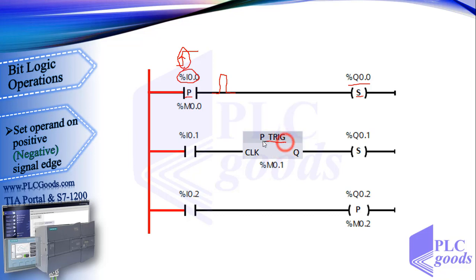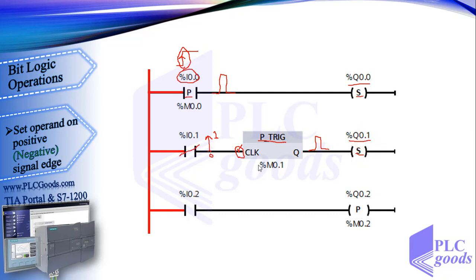This instruction queries a zero-to-one change in the signal state of the RLO at its input. When I0.1 changes to closed, the RLO changes from 0 to 1 at this input, and this block generates a pulse which sets Q0.1 to 1. In the last line, when I0.2 changes to closed, this instruction sets its output to 1 for just one program cycle.